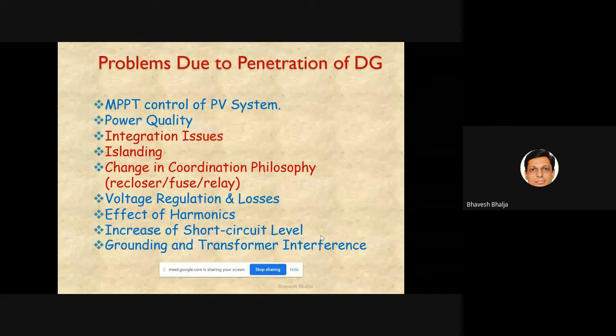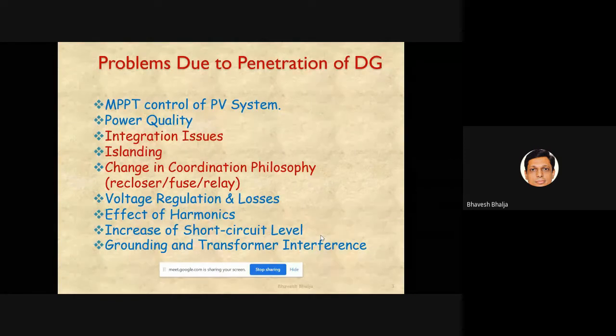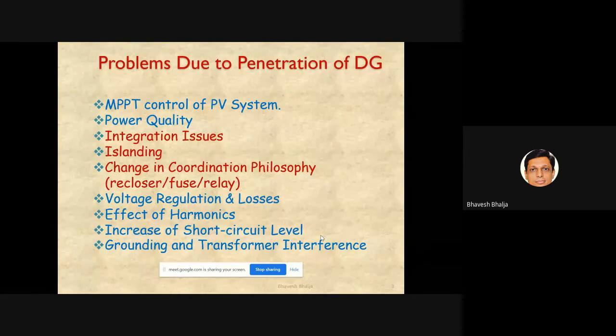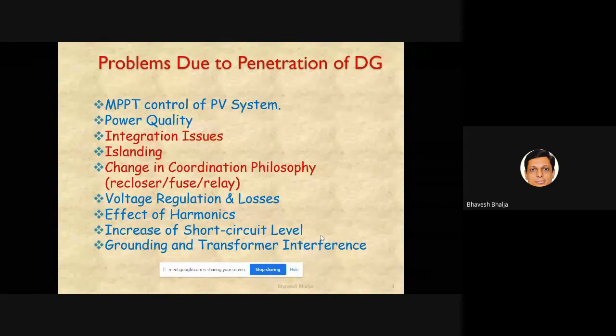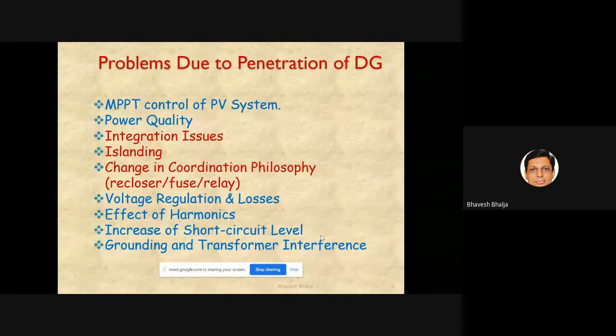If I have, let's say, 11 feeders in a substation, then I need 11 circuit breakers. If fault MVA or short circuit level increases because of the penetration of DGs, then I have to replace all circuit breakers, because otherwise they are not capable to withstand that much fault power. This is a major issue. Nowadays utilities are doing retrofitting as a part of the solution for this.